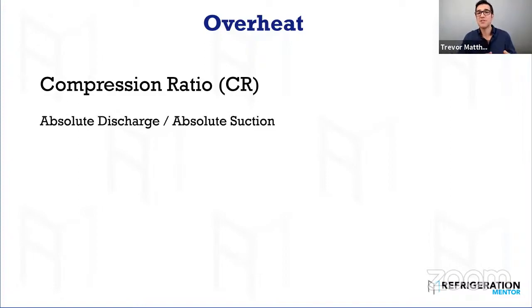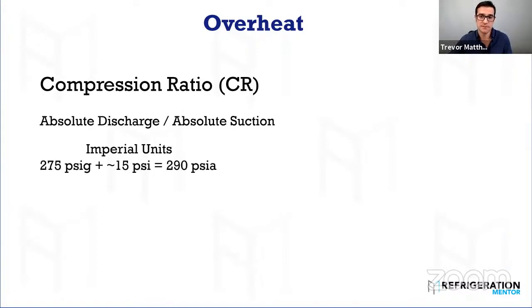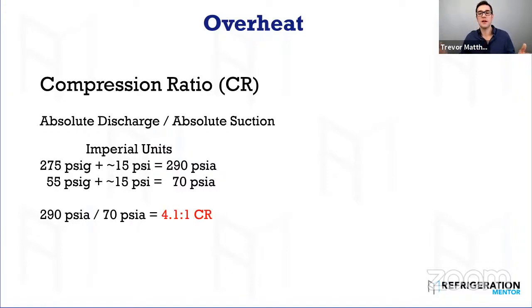So what is it? Absolute discharge over absolute suction. How do you get absolute? In imperial units, you take your gauge pressure, 275 psi, plus atmospheric, 14.7. I just use 15, it makes it easier. That's 290 psi A. Then we get into the suction. Got to turn that to absolute. So 55 psi G plus 14.7, which I do as 15, is 70 psi A. So this is a 4-to-1 compression ratio, which is probably pretty good for that specific system.